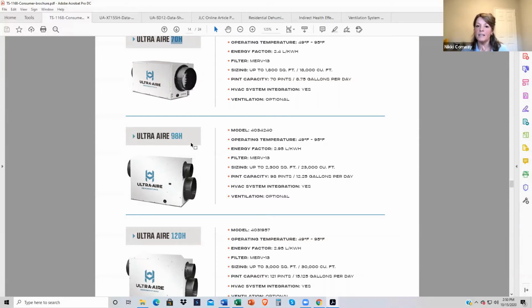If we are minimizing our infiltration as much as possible, adding a dehumidifier to a system, and if it's the right size dehumidifier, and we're not looking at astronomical numbers in ventilation here, a dehumidifier should be able to handle it, usually in conjunction with some air conditioning. It should be able to handle those two systems together, and handle the moisture loads from adding ventilation, even a little bit of additional ventilation in a home.